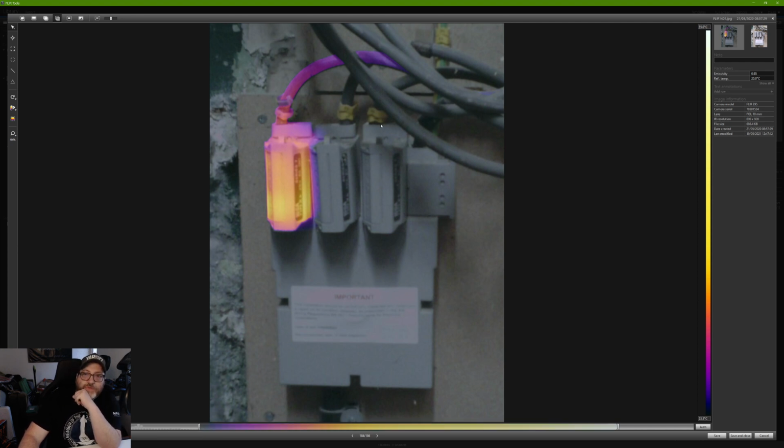Now what I'll do is I've got a lot of this color here, which is coming from around the bottom of the fuse, and I've got this color along the cable. So I'm just going to manually lift the bottom end. This lifting here, if I drag this to the right, look at the number here, this goes up. So I'm lifting the bottom. Okay, and when I do that, lifting the bottom, what I'm doing is I'm chasing in all the darker color, which is the cooler temperature. So I want to lift the bottom here, just to chase this color down the cable a little bit, just so that this is really where all the drama is happening. So you'll see it's just retreating back to the fuse.